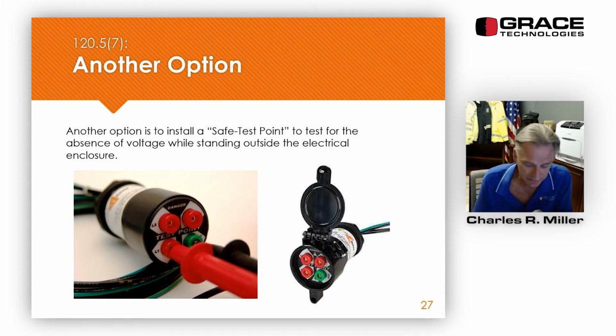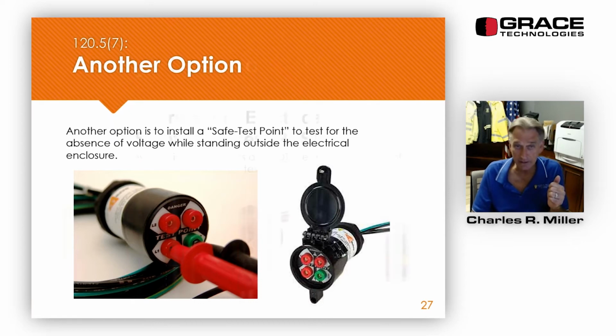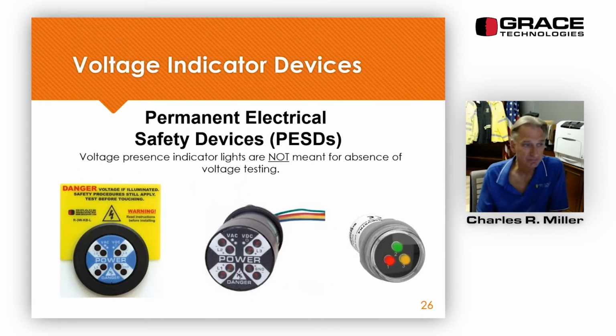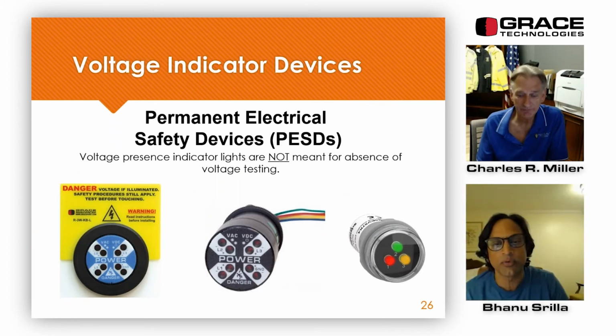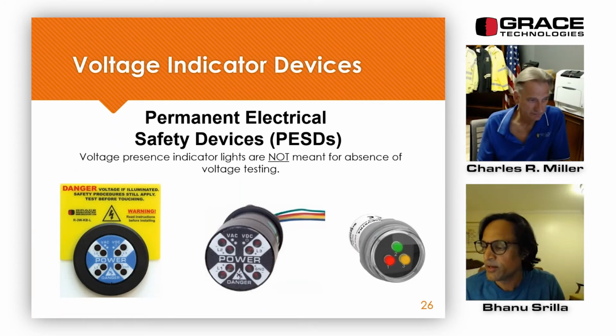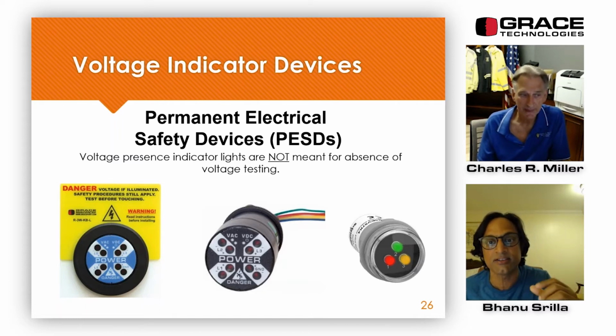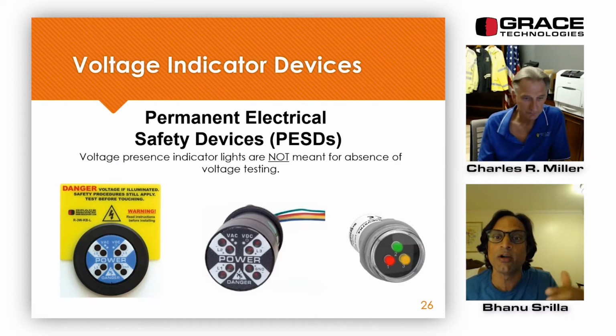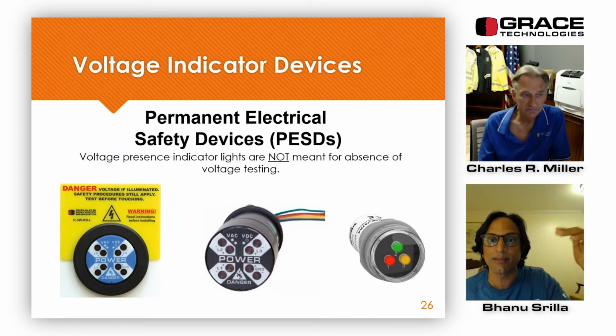Charlie, do you want me to just make a quick comment on the previous slide, if you don't mind? Just go to the previous slide. Yes. So I just want to reiterate the points Charlie mentioned about Article 120.5, whereas in step 3, he talked about visually verifying the blades, and there is also step 4, which is a release of stored energy. These devices can be used to visually verify the voltage presence that meets step 3 and step 4.